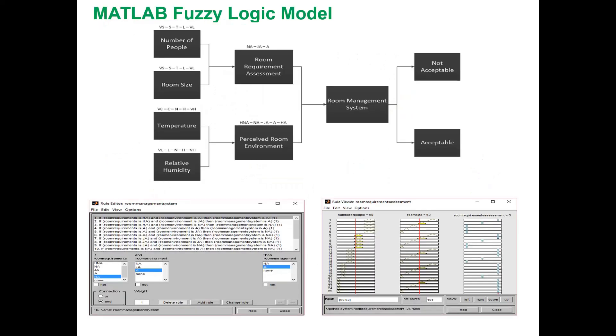The temperature and relative humidity information retrieved through sensors will be stored in the database. The Fuzzy Logic control mechanism will acquire data from the database and compare the temperature and relative humidity parameters with predefined standards, calculate the degrees of membership, and obtain output using the classification method. There were 25 rules generated for five conditions with respect to identified parameters. The ranges and specifications of the elements are acquired from ASHRAE Standard 55-2010, which recommends desirable levels of indoor comfortable environment.